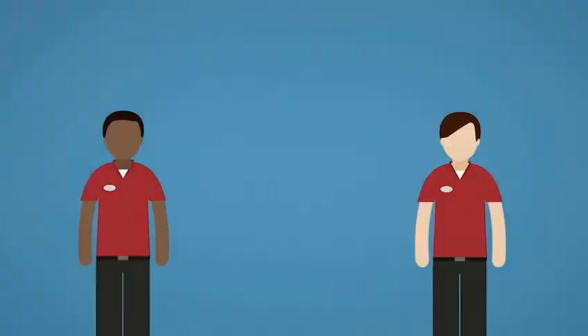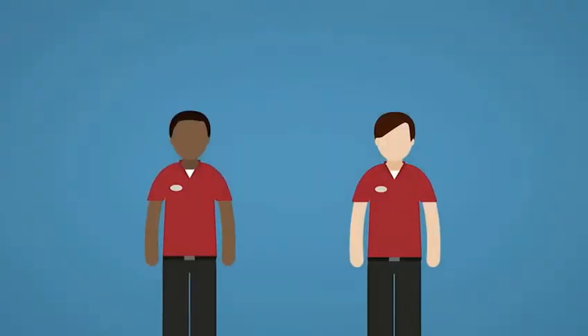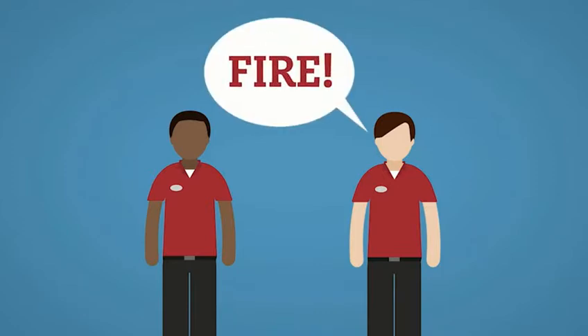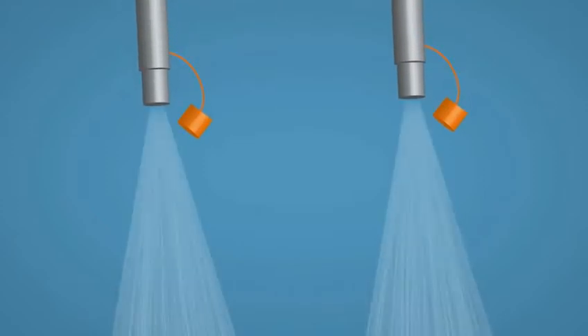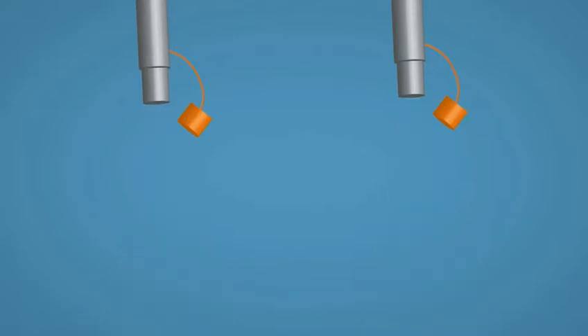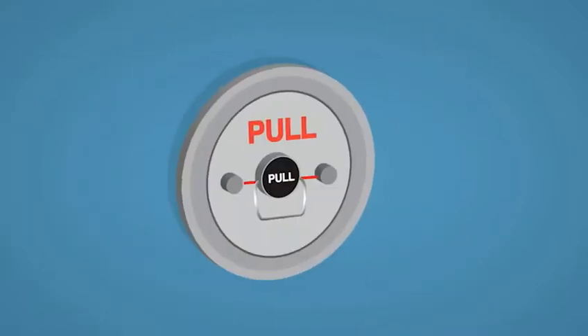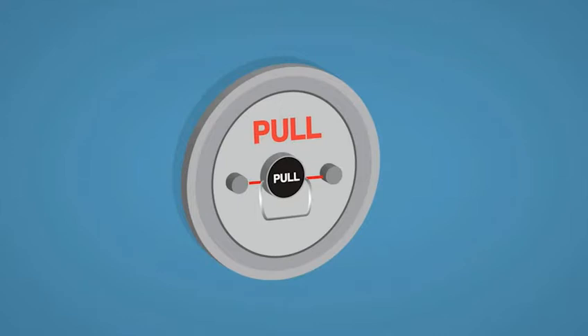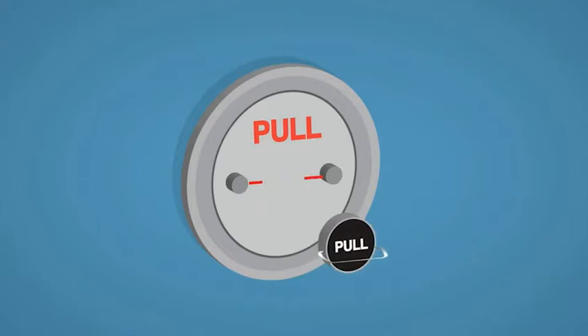If a fire does break out, you'll need to take action quickly. At the first sign of a fire, notify restaurant leadership. If a fryer catches fire, leave it under the vent hood so that the Ansul system can do its job and contain the flames. If for any reason the Ansul system does not go off automatically, here's what you should do. Trip the Ansul system manually. To activate, you'll pull on this ring at the pull station. This will break the thin glass bar and activate the system.